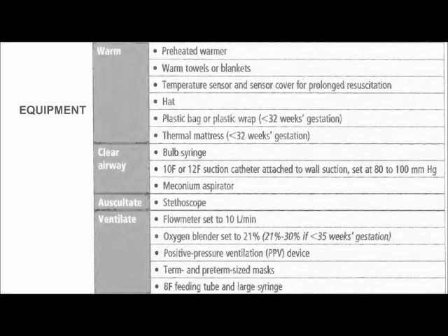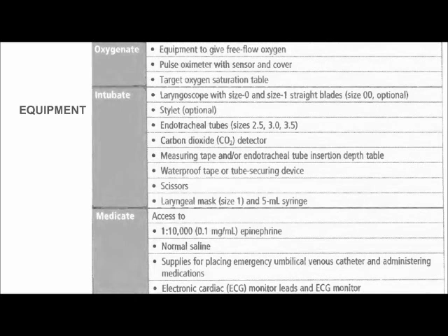And for oxygenation, equipment to give free flow oxygen should be checked, and a pulse oximeter with sensor and target oxygen saturation table is also a must. For intubation, a laryngoscope with size 0 and size 1 straight blade, size 00 for preterm less than 28 weeker, and ET tube size according to the gestational age, and a measuring tape and ET tube insertion depth table are also checked. And in medication, injection adrenaline in 1 to 10,000 dilution, and normal saline are checked.